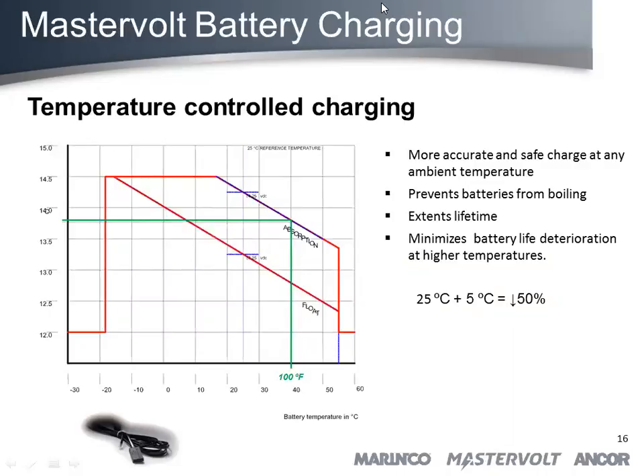Yes, sir. The temperature sensors, I constantly see the little sticky back units, and I constantly see them knocked off. Do they still function if they're not adhered to the battery but just sitting on it? Ideally, we put them between batteries, because that's the hottest spot. But technically, it's measuring also the ambient temperature. Yeah, I see people stick them right on the top of the battery, but then somebody goes in there and while they're working, they step on it and the darn thing gets knocked off.